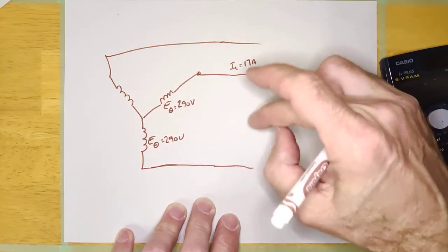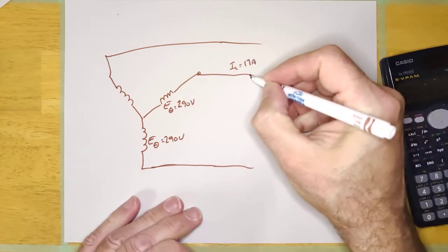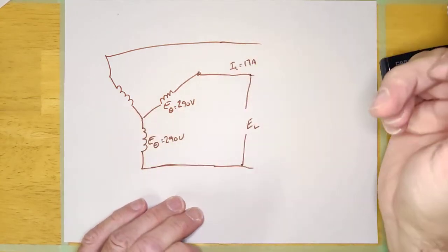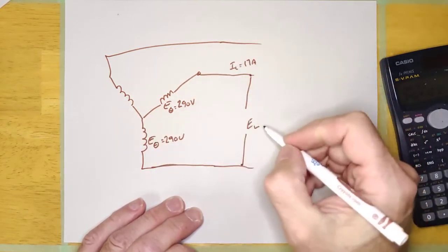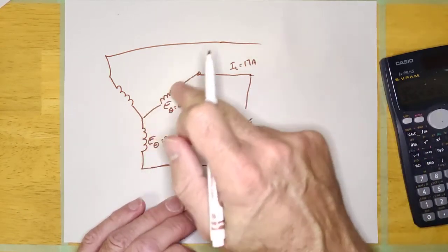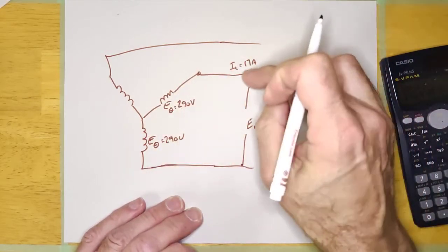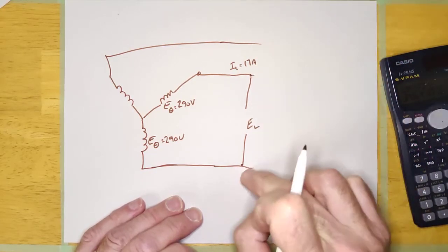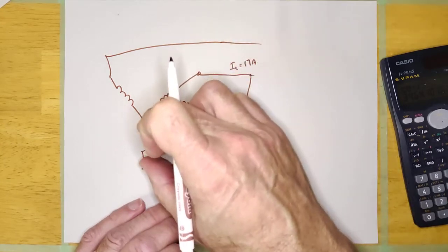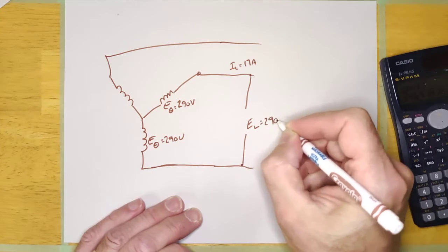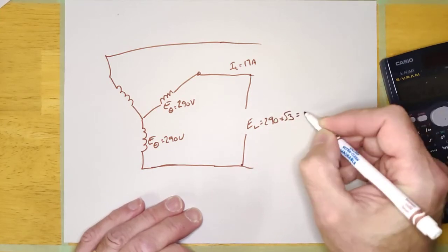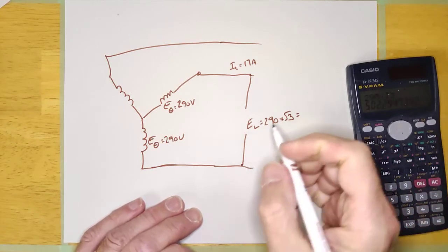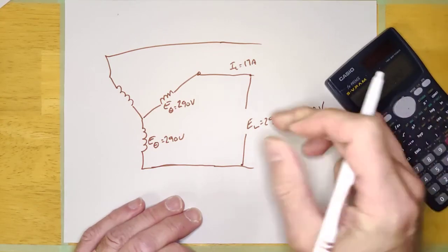But when you're measuring the line voltage, guys, you're moving your meter leads, one of them at least, right? Now you're moving it to there, E line. So imagine yourself measuring that voltage, okay? Because literally I get people saying E line is 290, and they say it is because it's connected to the phase, and the phase is 290. So that line must be 290. But that line is nothing, okay? That line is 290 from here to somewhere else, to here. And it's that 290 plus that 290, so this will be 290 times root 3, whatever that is, 503. Okay, guys?